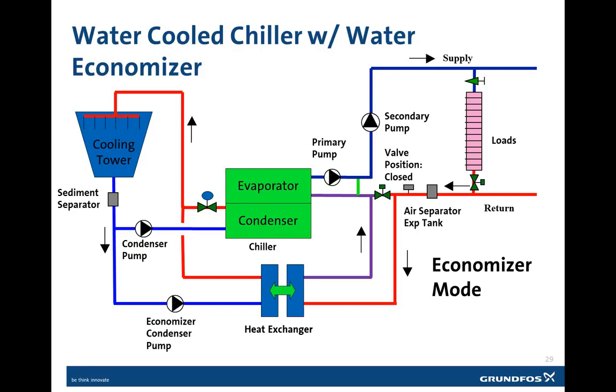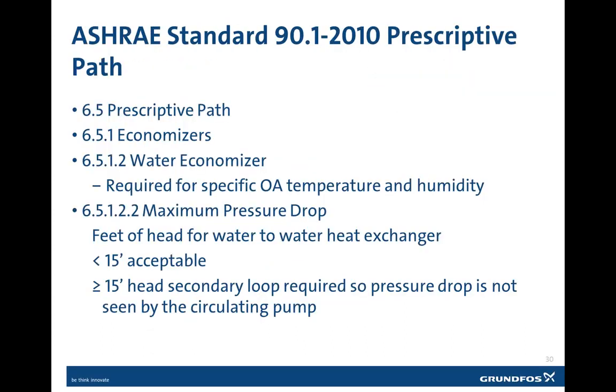Now that we understand a water economizer and a little bit of how that impacts the piping configuration, we can discuss a little bit of the implication of this with the ASHRAE Standard 90.1. Now, the fact that the economizer is required is straightforward in this application, but the maximum pressure drop requirements need a little bit of additional explanation. So the head, or the pressure drop associated with the heat exchanger, must not exceed 15 feet of head of water, or a secondary loop must be created in the system per 90.1. The purpose of the secondary loop is to ensure that the pressure drop is not seen by the pump during the normal cooling operation.